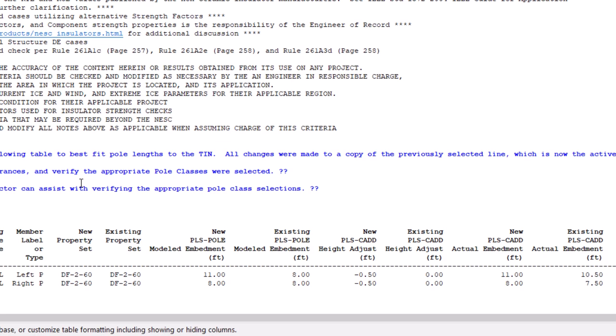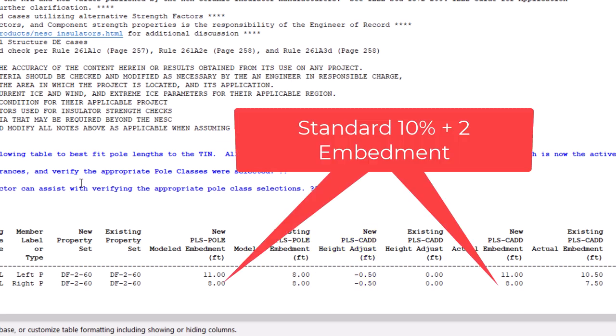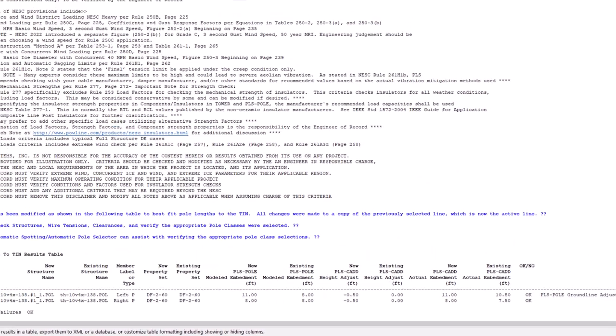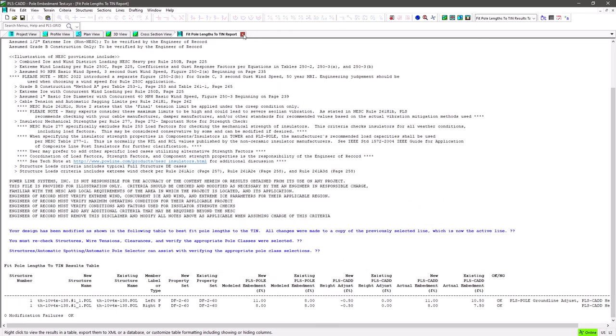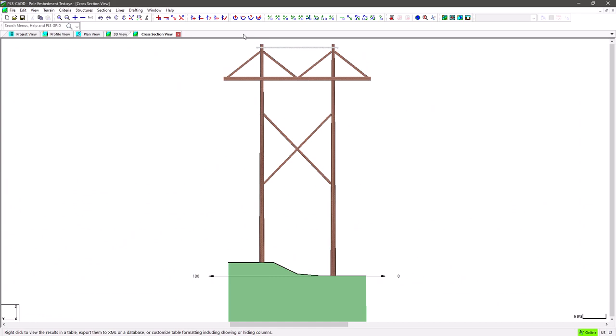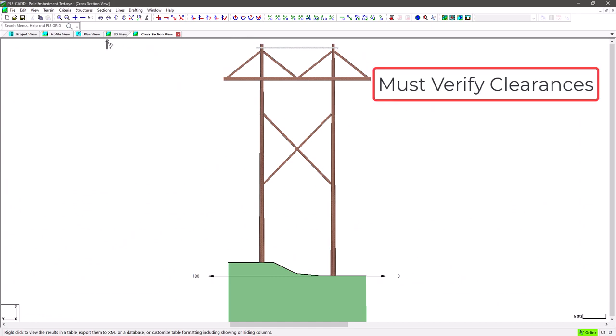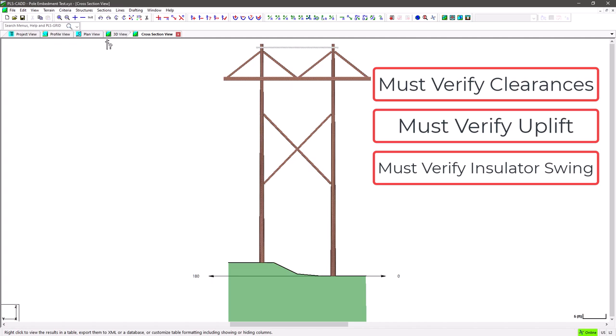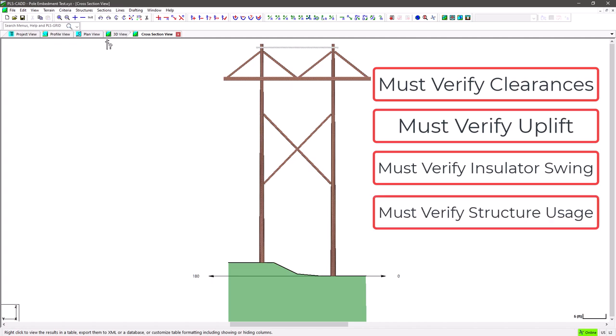In the case of this structure, it is lowered by 0.5 feet so that the right pole has a perfect 10% plus 2 embedment and the left pole goes 3 feet below the tin surface and needs to be over embedded by 3 feet for a total of 11 feet. Please note that when using these features to adjust the height of a structure, it is imperative to verify clearances, uplift, insulator swing, etc., and regardless of any options chosen, it's imperative to reanalyze the structure.